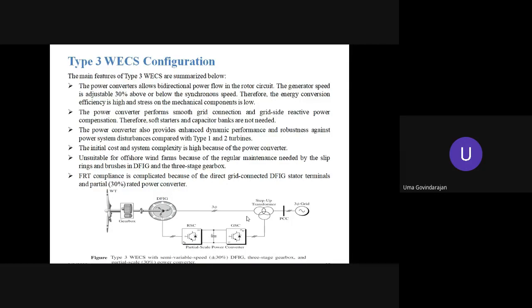Now here we are employing a partial scale power converter, both on the rotor side as well as on the stator side. Both subsynchronous and supersynchronous operation are possible. Below the rated speed and above the rated speed, both are possible. And when the machine runs above the rated speed, it is similar to type 2. Similar to type 2, the rotor slip power we can convert into DC, and once again convert into AC, and feed it into the grid.